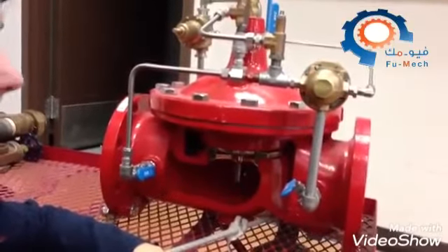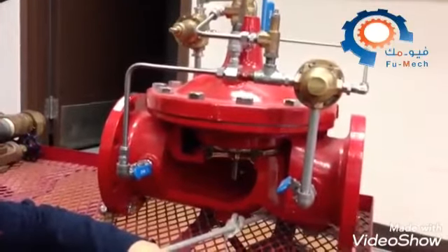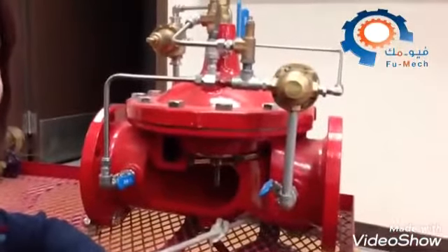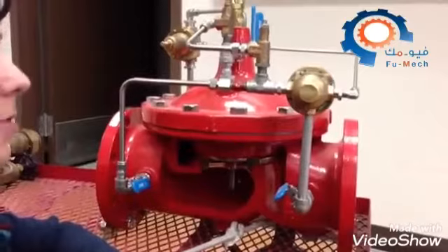What's the most common failure? What is the common failure of this? Plugged up? I don't know. No, the diaphragm fails. Oh, okay.